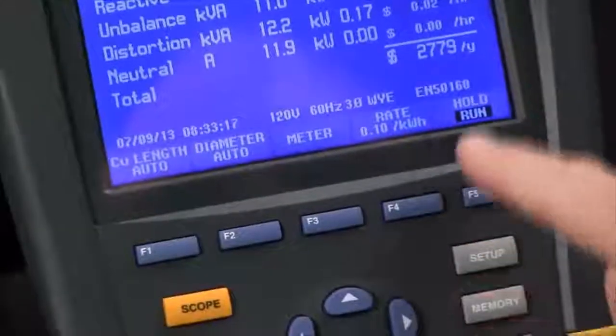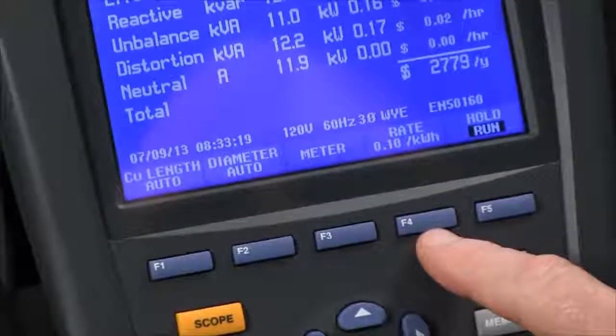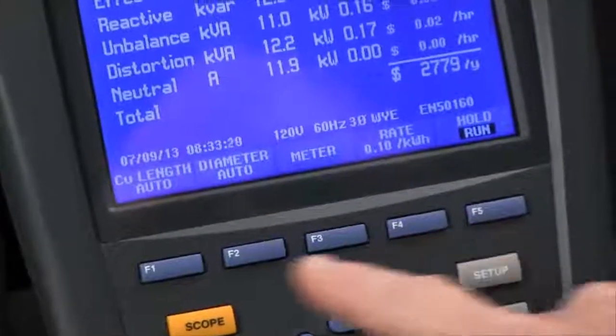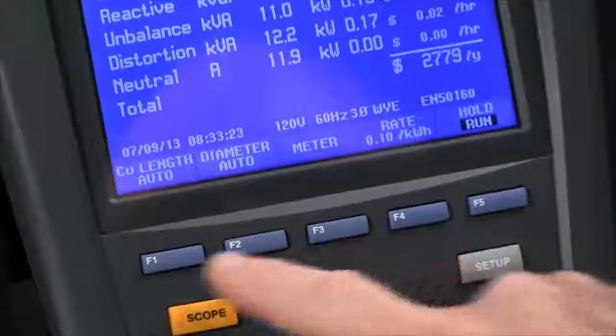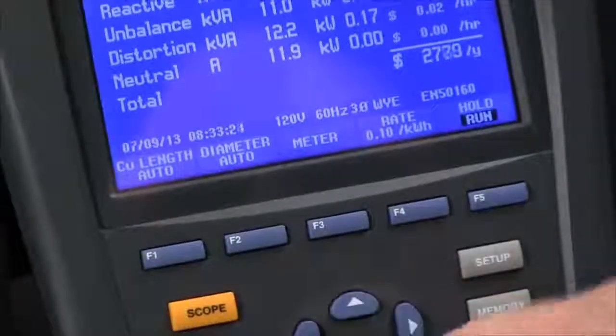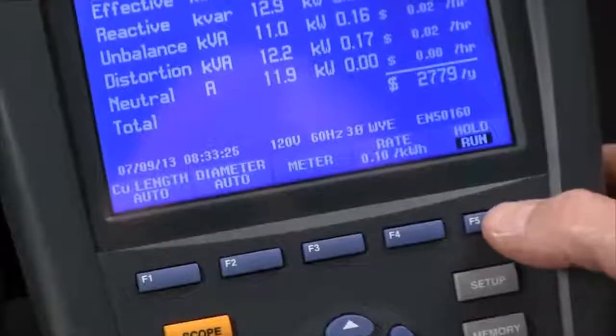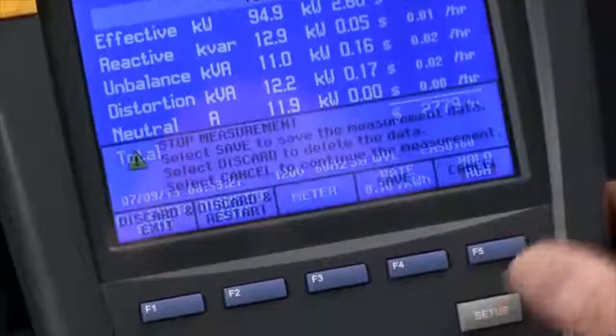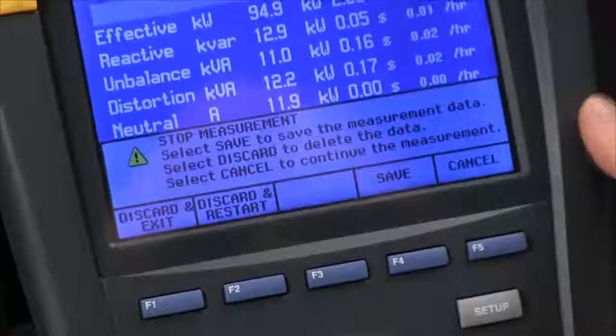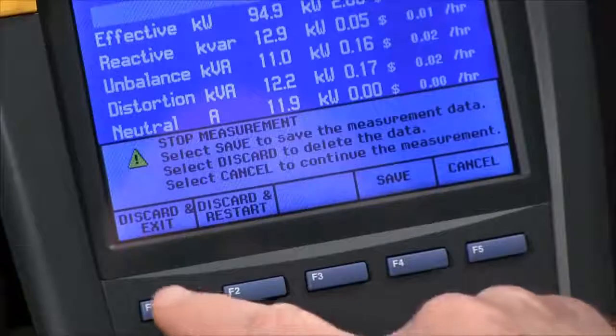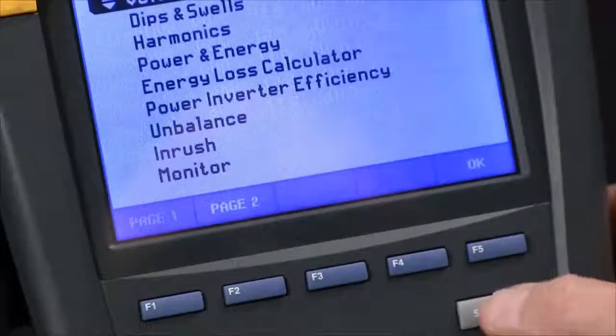We can configure the Fluke 435 to give us an accurate reading by telling it what our cost is per kilowatt hour and what our cable looks like, but we can't change those parameters from inside the test. So we have to hit the hold/run button to stop the test. We'll say discard and exit.